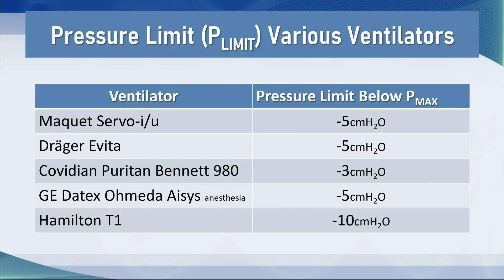This is the pressure limit for various ventilators. For the Maquet Servo I and U, it's minus five — the same for the Draeger Evita, minus five. The Puritan Bennett is minus three and the Hamilton T1 is minus ten. So if you set 30 as your Pmax on the Hamilton, the pressure limit is going to be 20 on pressure support. Be careful using the Hamilton that you give the patient enough space to get sufficient pressure support to ensure they get the tidal volume you're looking for.